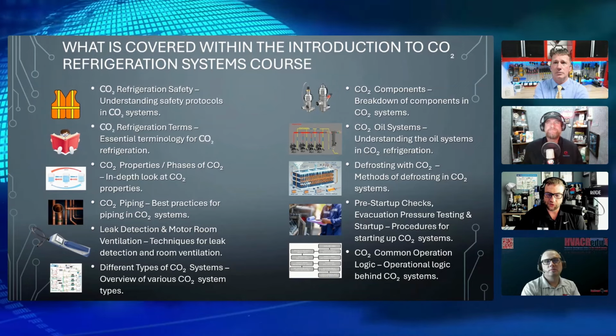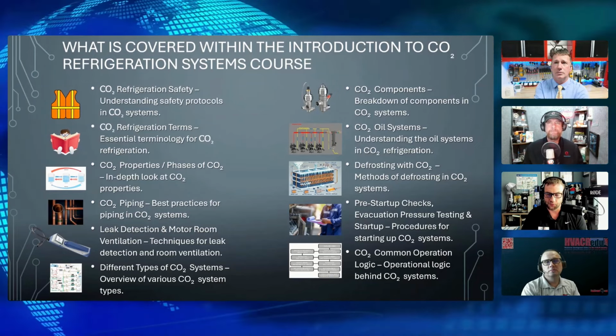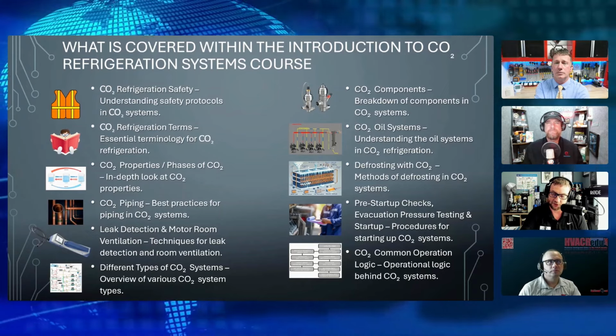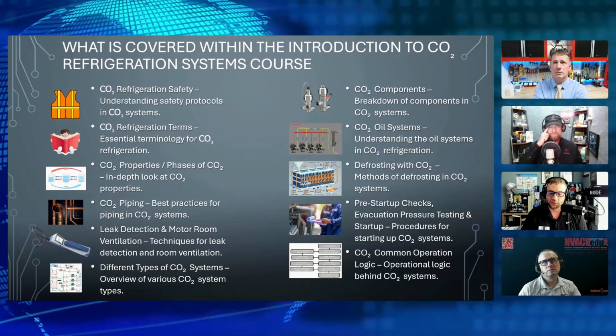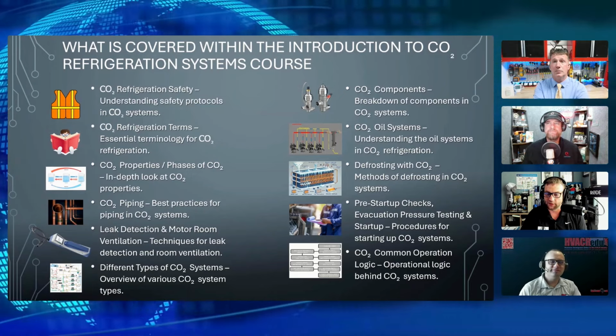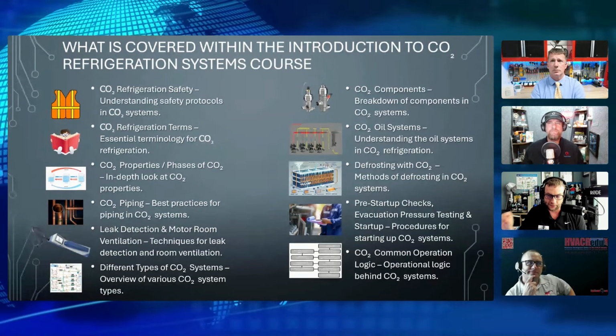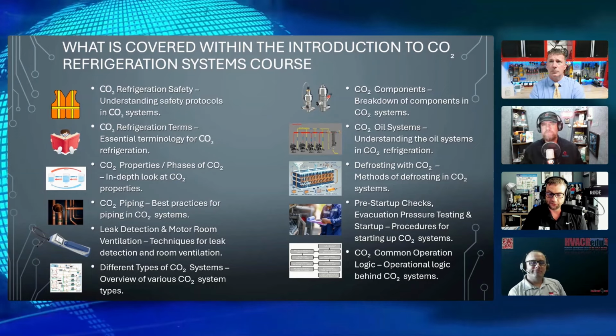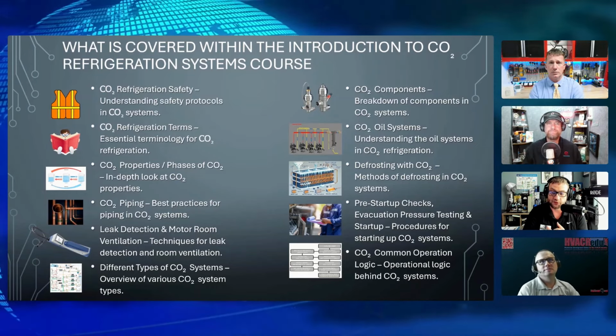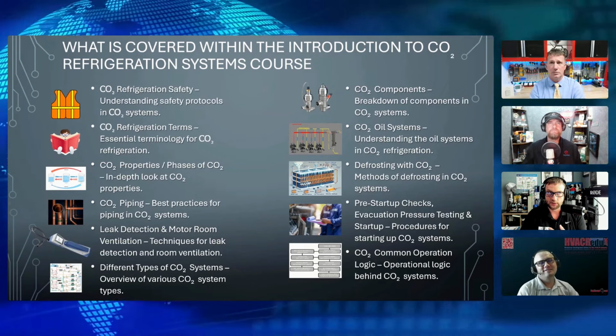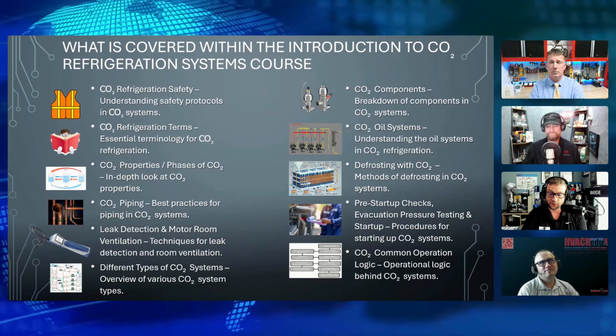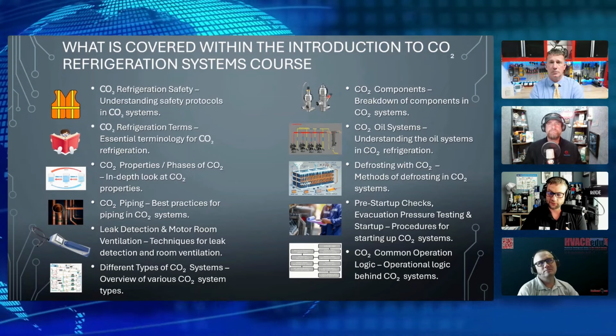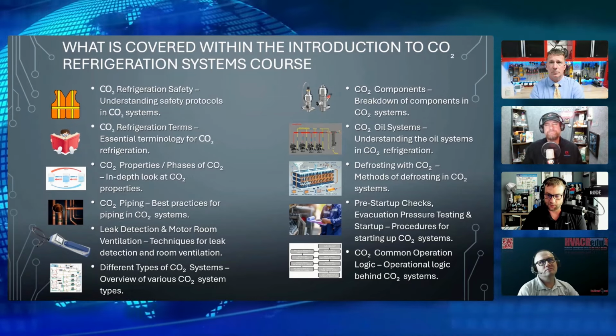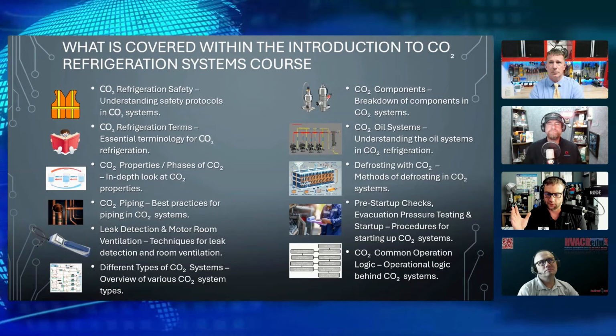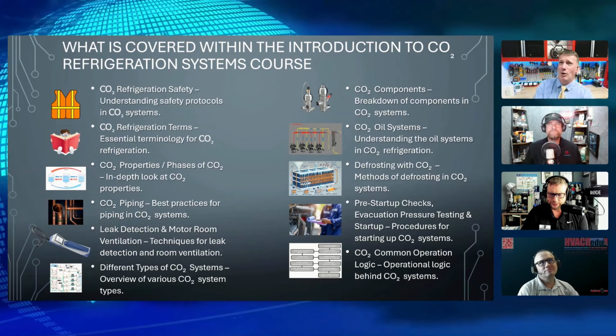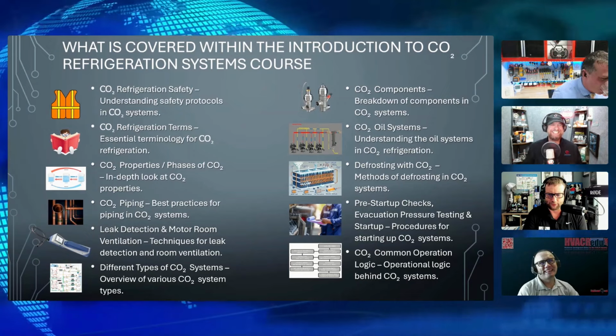Gotcha. Procedures for starting up CO2. There has to be a certain way to actually start these systems up. That segues right into our next section, which is CO2 common operation and logic. Every rack has its own little thing that it does, right? But when starting up a transcritical system, the sequence of operation is that we have to make sure there are no major alarms, no high pressure, no phase loss, right? Then the compressors are enabled. We start turning on two or three circuits, because CO2 has such a high BTU per pound that we can't just turn them all on at the same time and hope for the best. You don't want to pull all that heat back? No, it doesn't like it at all.